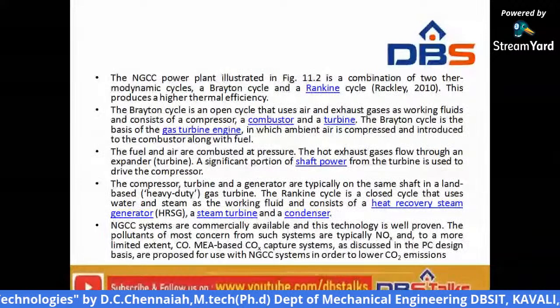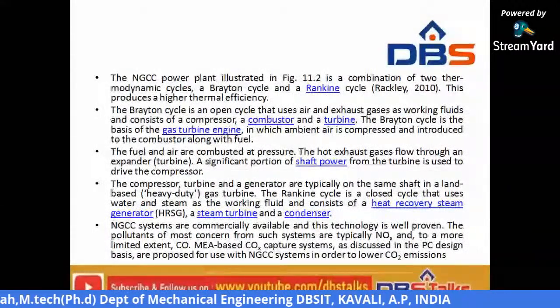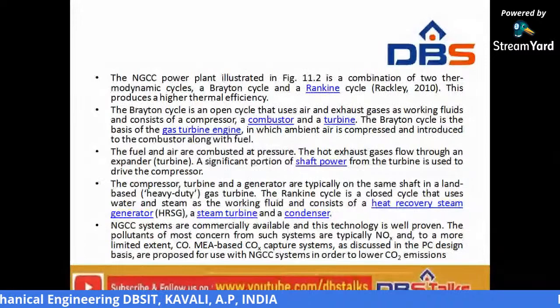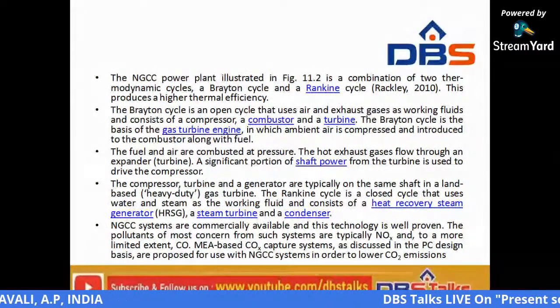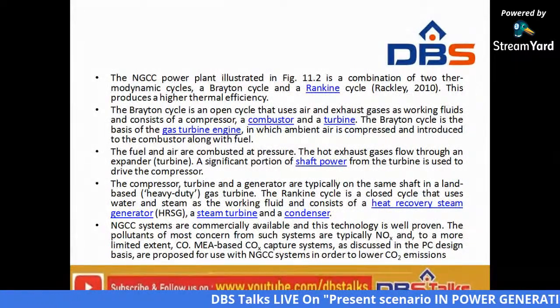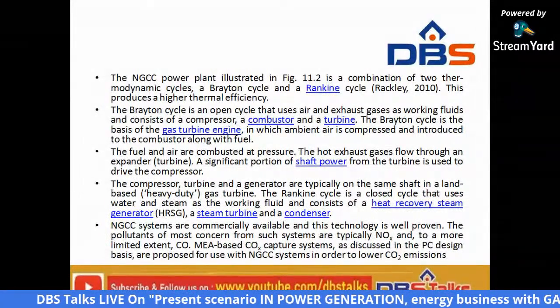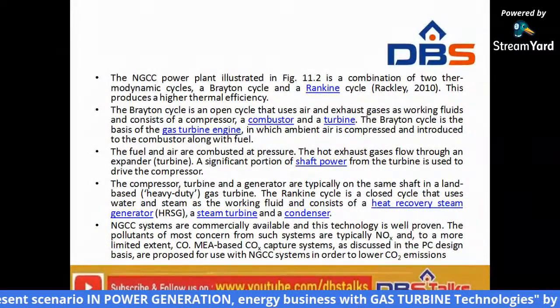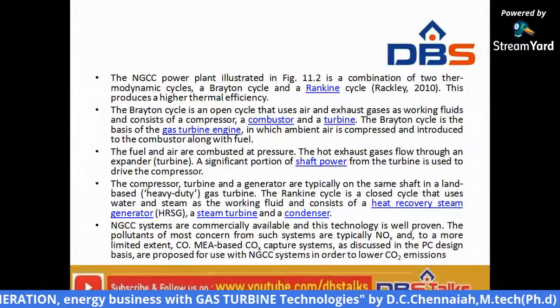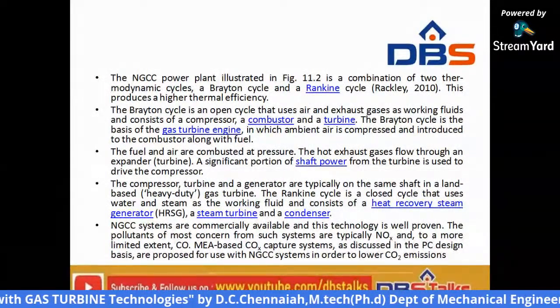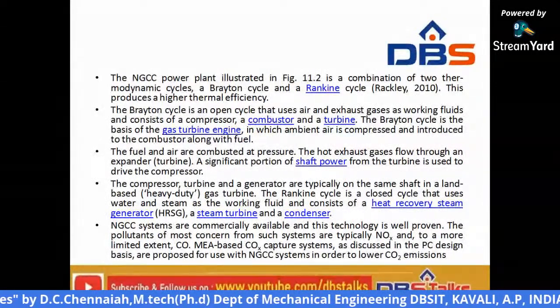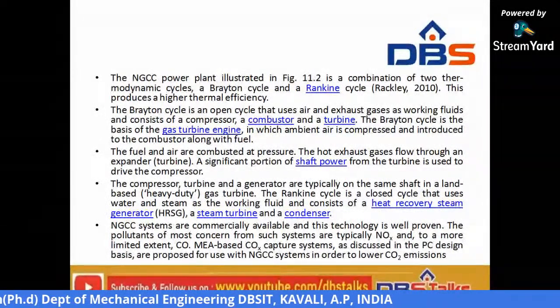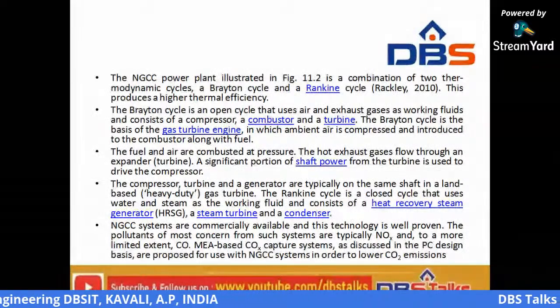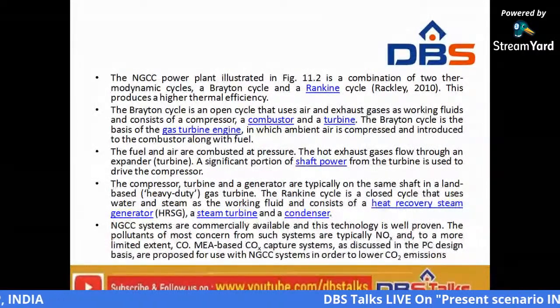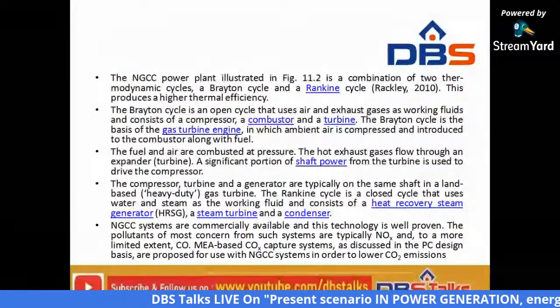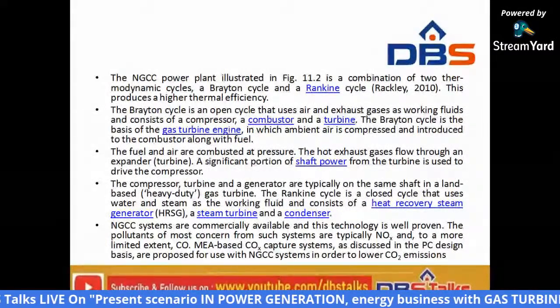As the latent heat is rejected to the cooling water, the steam phase changes from vapor to liquid. This liquid is nothing but condensate, which is water. It is pumped back to the hot well, and from there the water is pumped back to the heat recovery steam generator, which is nothing but the boiler, to form steam. Likewise, that fluid circulates throughout the closed circuit, which is why we call the Rankine cycle a closed cycle.